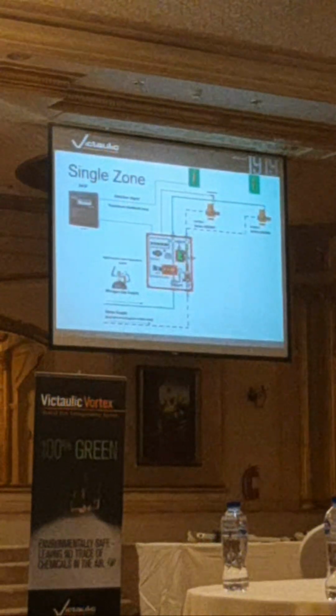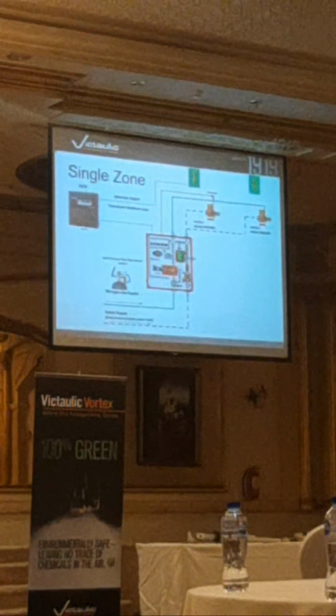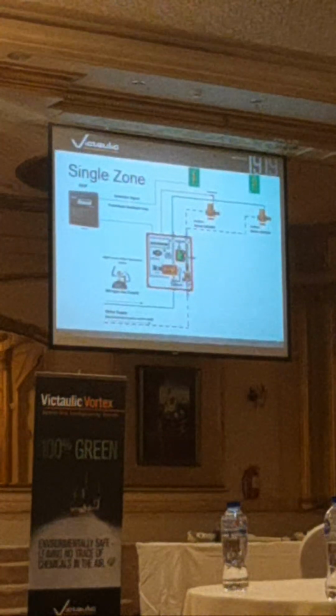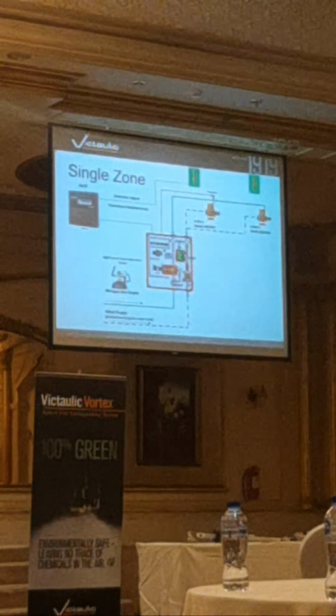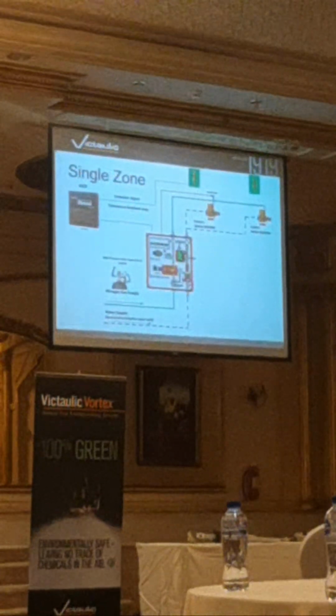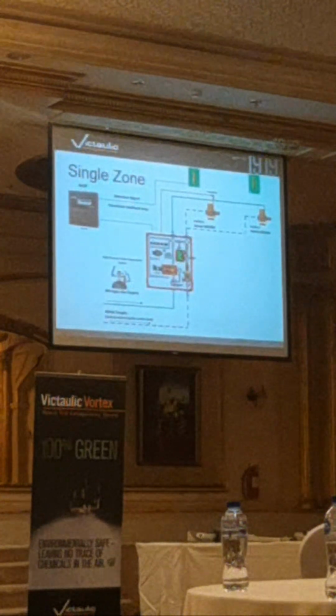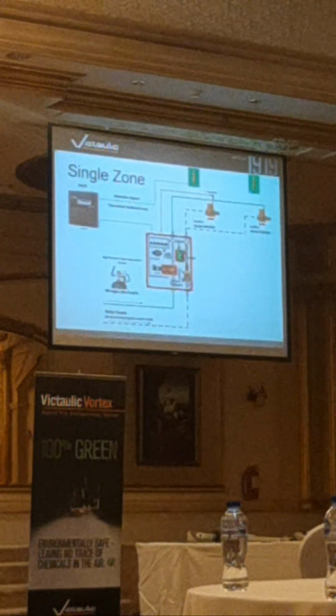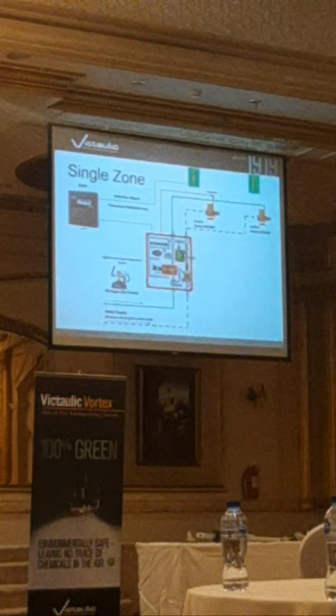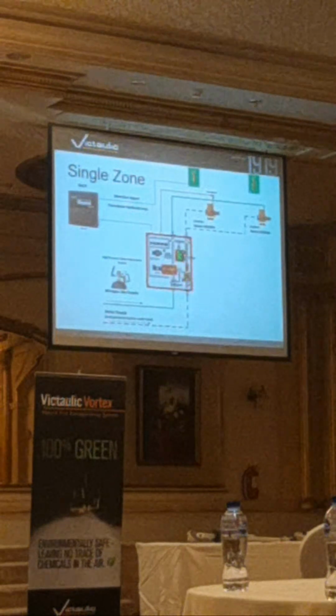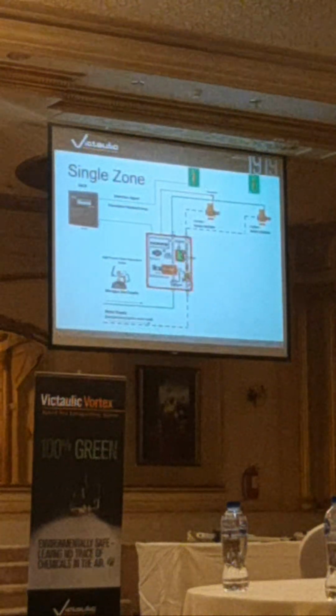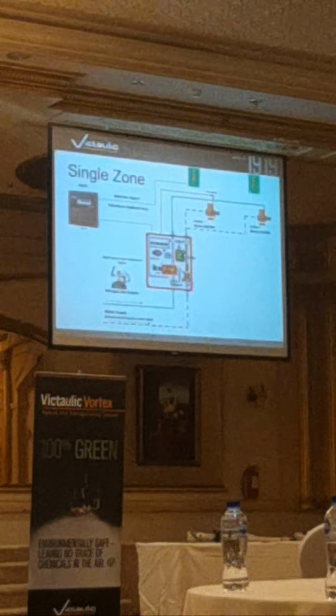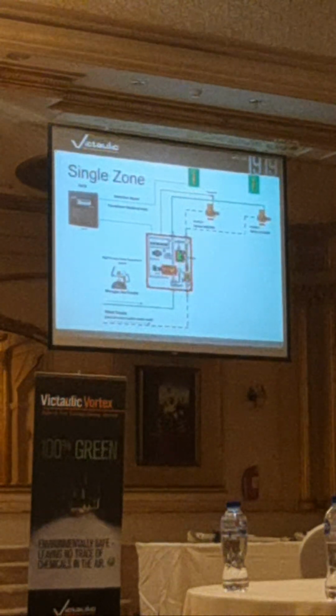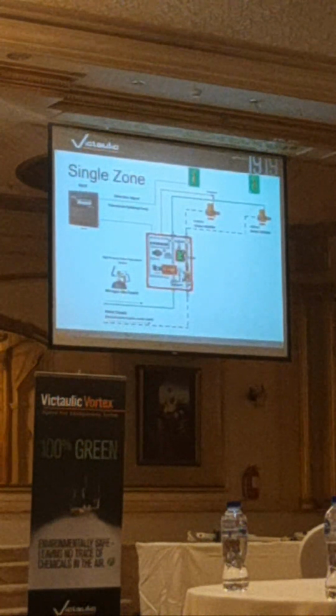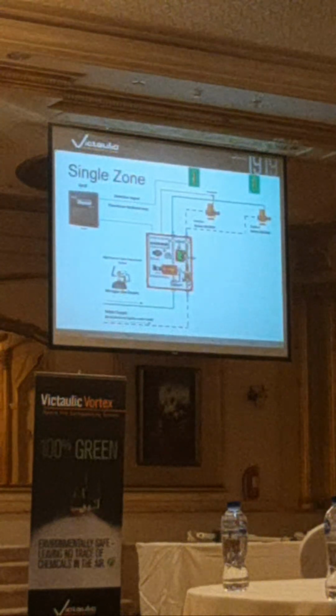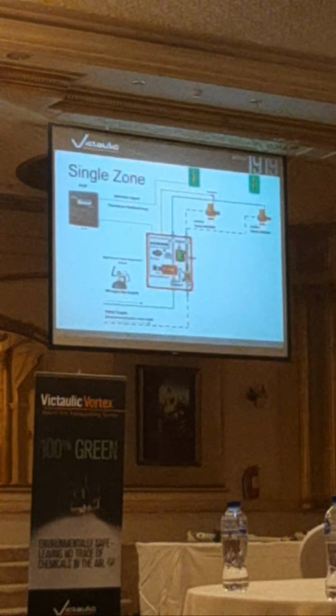The pressure transducer is a product that we're going to use to regulate the pressure, to look at the pressure downstream of the piping. So every emitter will need to have 1.7 bar, and that transducer will have a membrane inside. The more you push against it, the more signal is going to be returned to the panel. And that way the panel knows I have 1 bar at my nozzles, I need to increase, so I'm going to open up my valve.